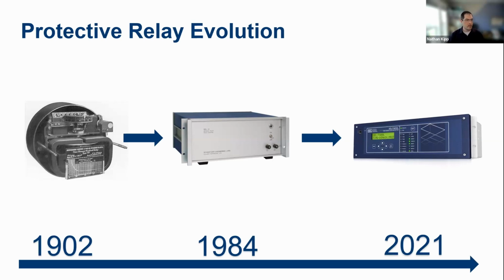Another benefit is now we can get data out of the relay. Prior to this, a relay was just a relay and it tripped or it didn't. But now we have sequence of event recorders. And so we know what happens. We can get some oscillography. We can say, okay, this happened at this point in time. And we can start to reconstruct events, which helps us improve the stability of the power system.